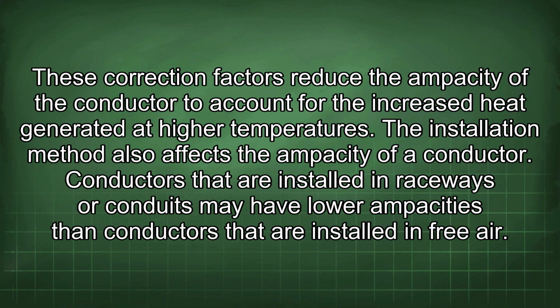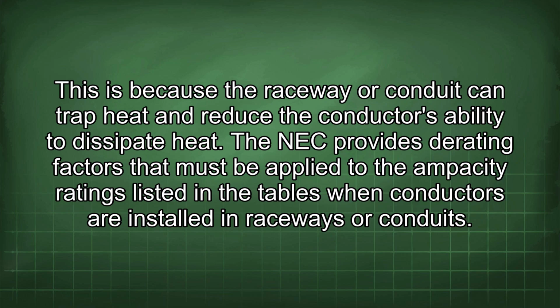The installation method also affects the ampacity of a conductor. Conductors that are installed in raceways or conduits may have lower ampacities than conductors that are installed in free air. This is because the raceway or conduit can trap heat and reduce the conductor's ability to dissipate heat. The NEC provides derating factors that must be applied to the ampacity ratings listed in the tables when conductors are installed in raceways or conduits.